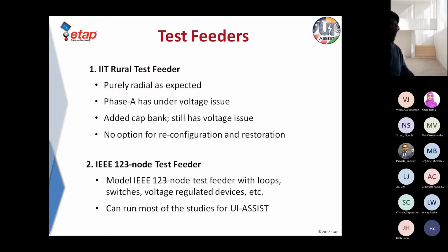In the IIT rural test feeder, as you've already seen, it is purely radial, which is expected since it's a rural feeder. Ravi already mentioned we have a voltage issue on phase A. I've seen the voltage go down to around 90, or even 87 or so, at the end user, which we did not expect. We're trying to improve that.